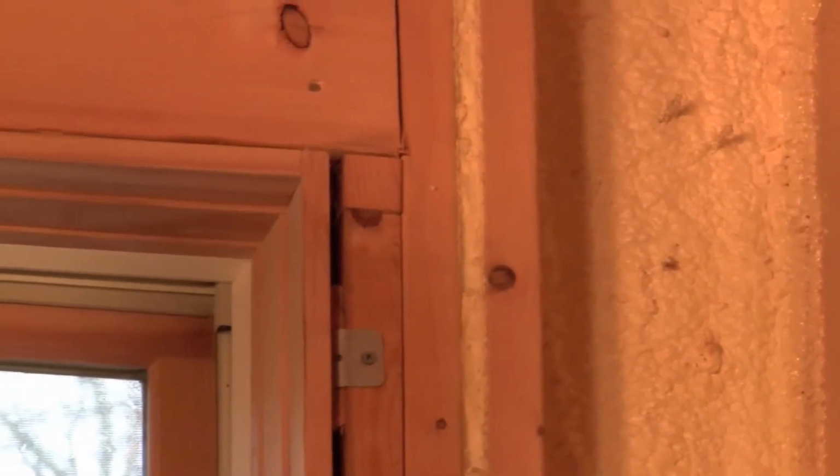Open cell insulation allows moisture to penetrate. It has a lower R factor, typically 2.5 to 3.25 per inch, versus the closed cell, which is about maybe 30% more expensive. It has an R factor of 6 to 7 per inch, and it will not allow water to penetrate into the property.